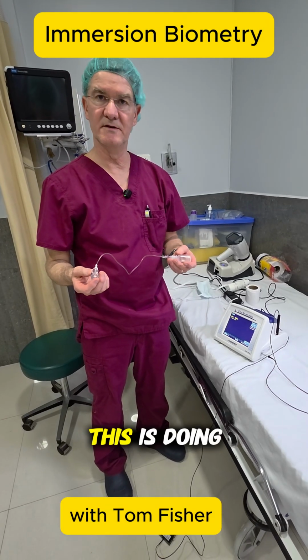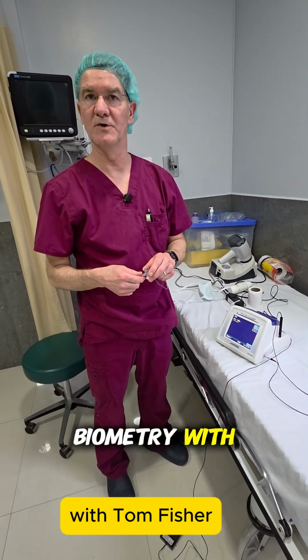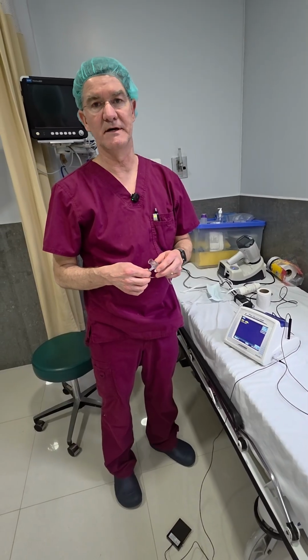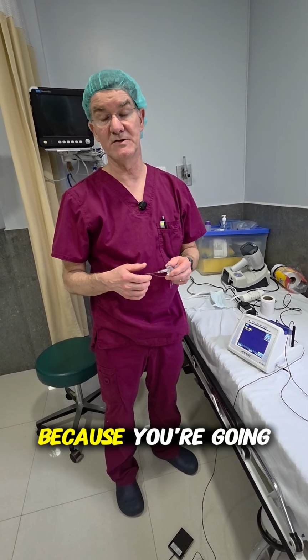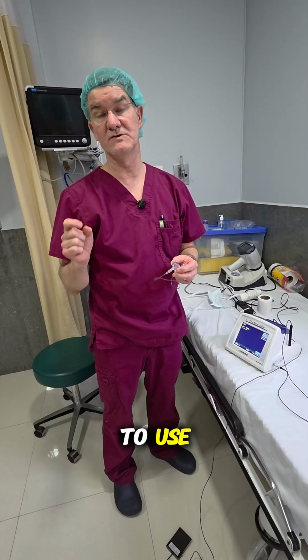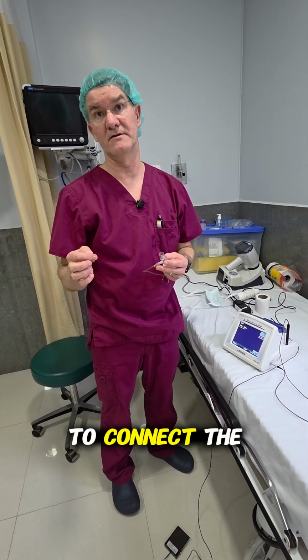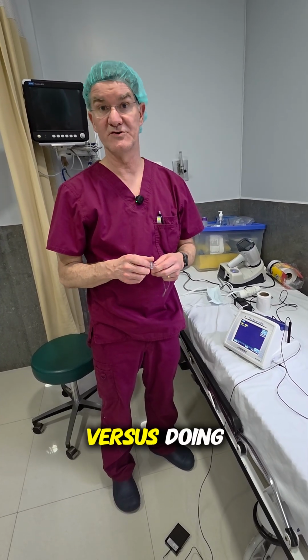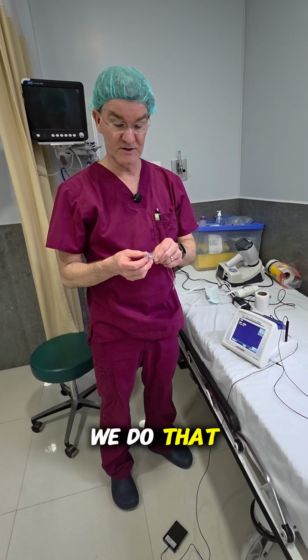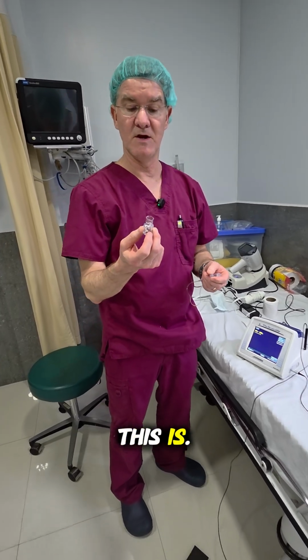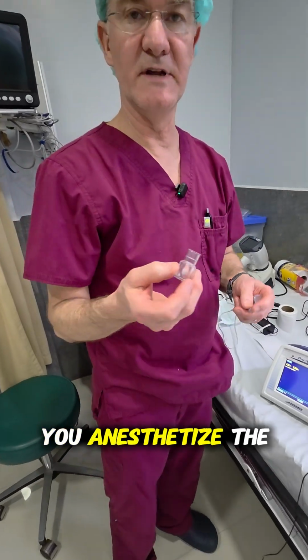So this is doing biometry with immersion. And you use immersion because you're going to use saline solution to connect the ultrasound probe to the eye versus doing applanation. How we do that is with a Prager shell, which is what this is. So a Prager shell simply goes, you anesthetize the eye.